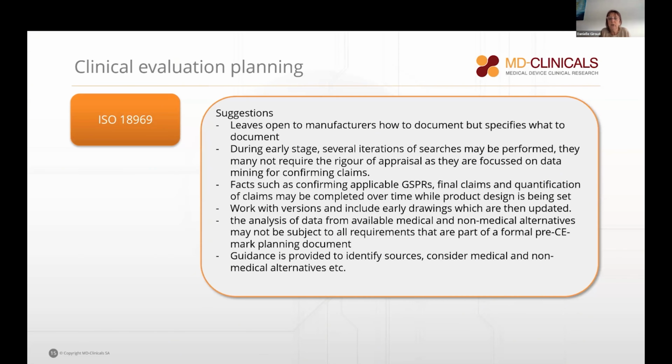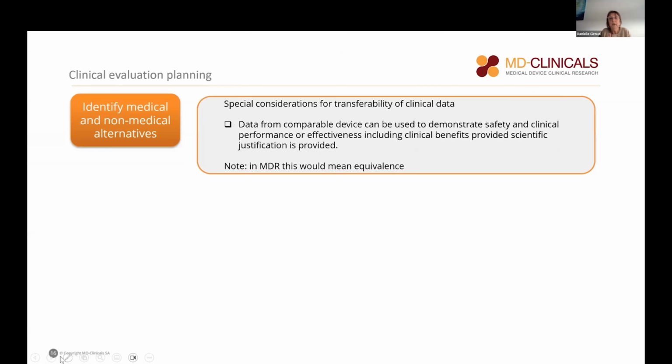So guidance is provided on sources, considerations for medical and non-medical alternatives, and then we have some special considerations on transferability of clinical data. We are not using the term equivalence. This is a regulatory term for us. In the process, we just say there are regulations that may allow you to transfer data from one device to another, and then go to these regulations. We give the links to the regulations, but we're not a regulatory document.